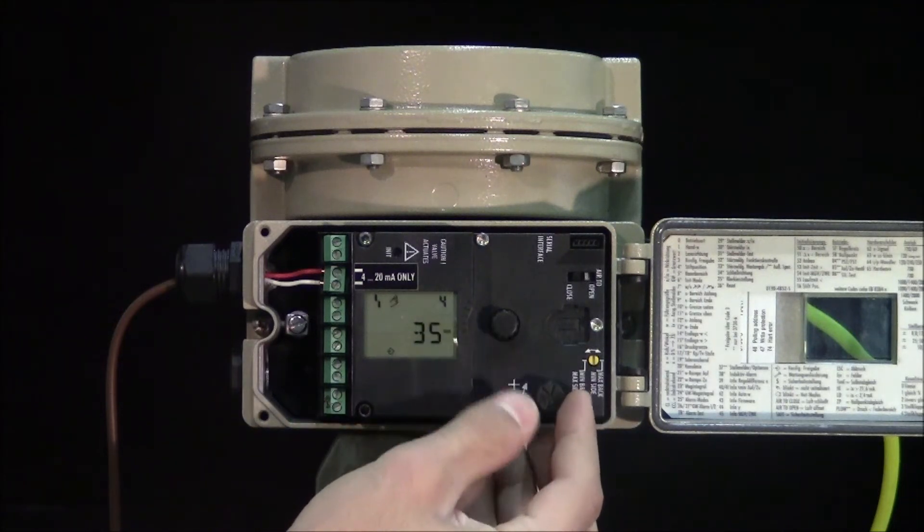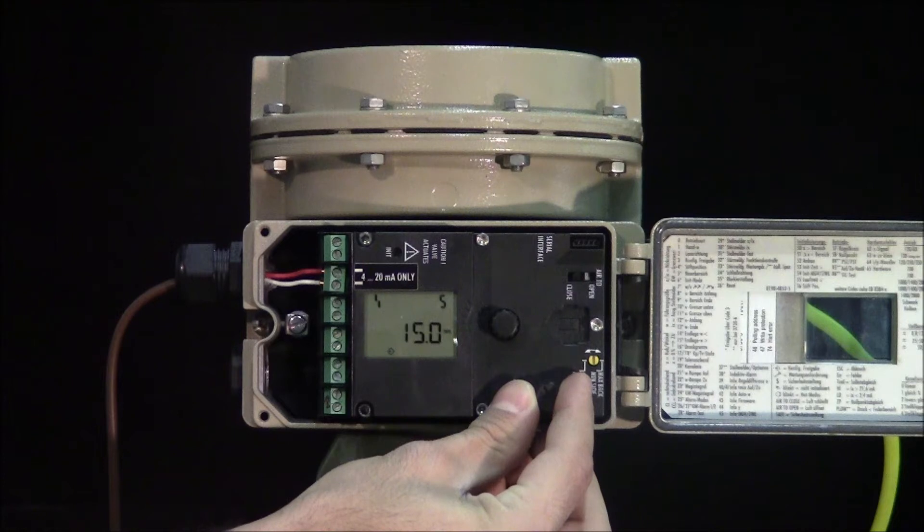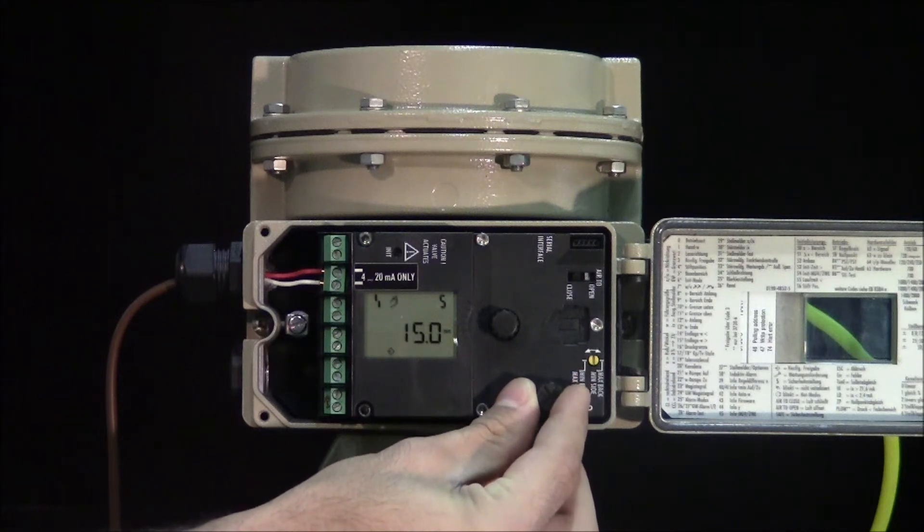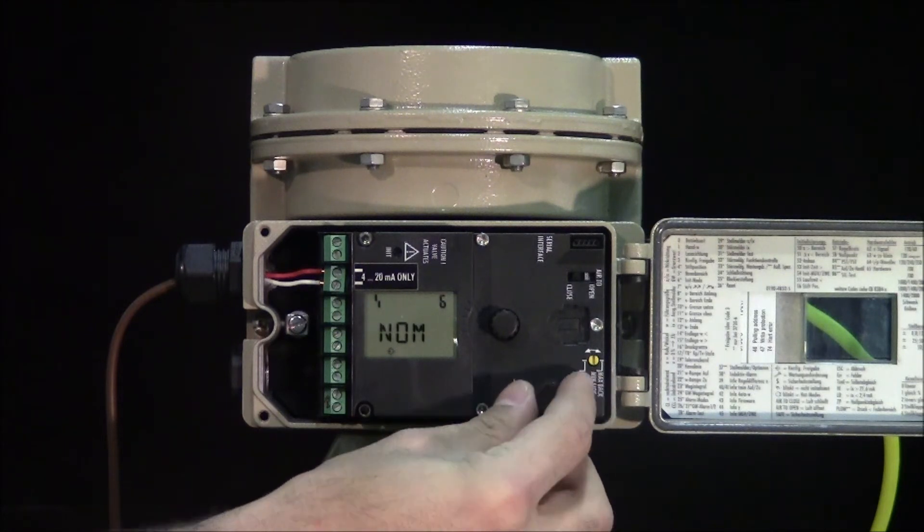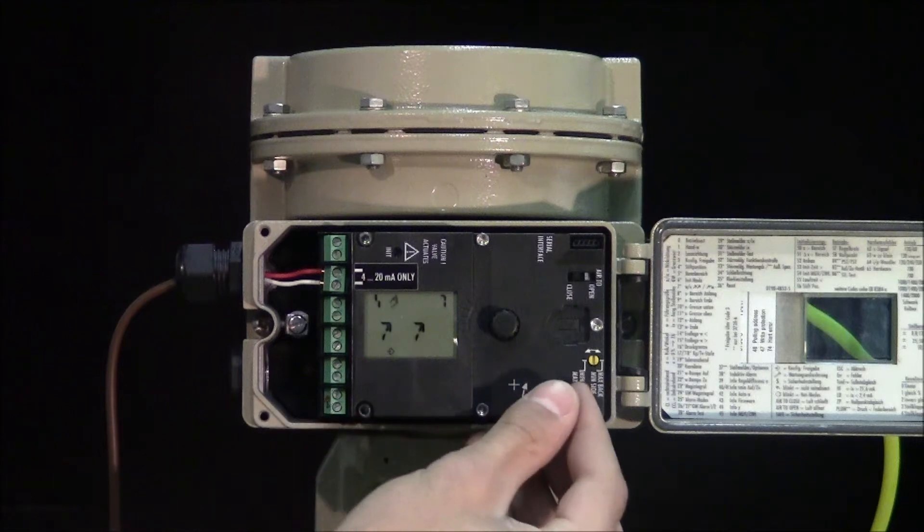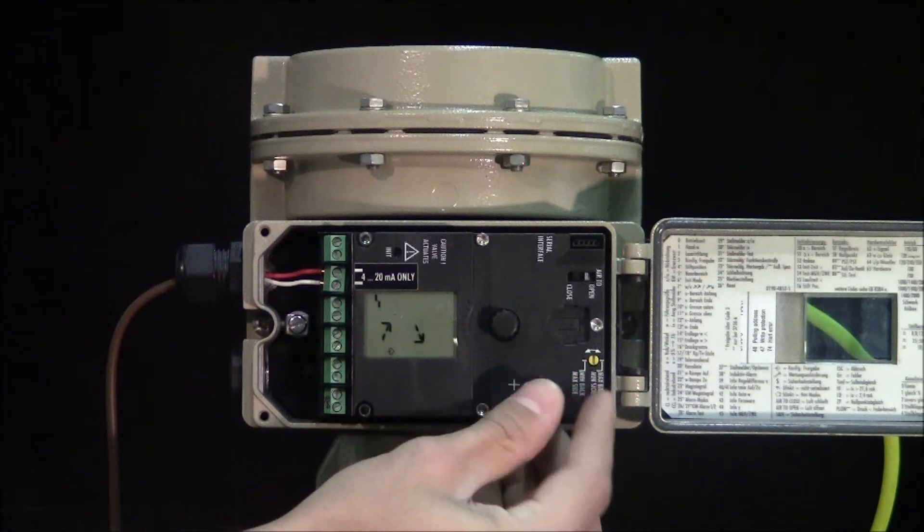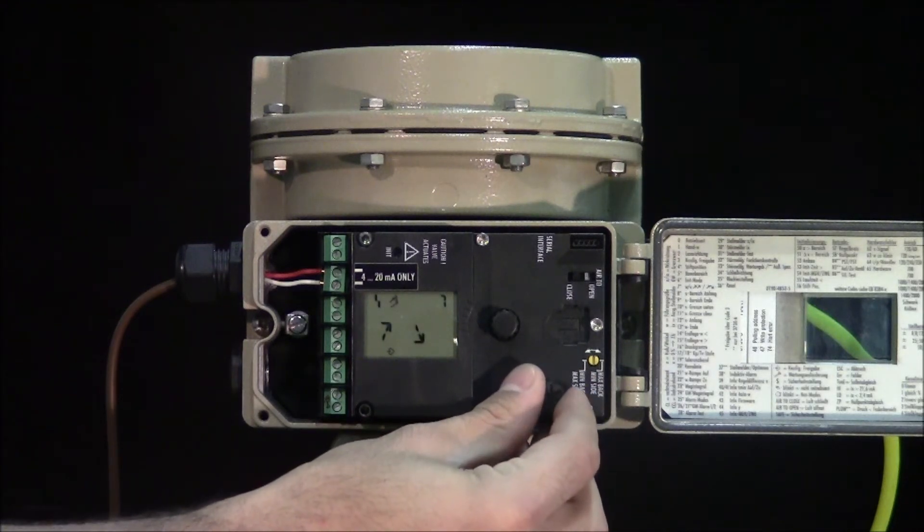Parameter 4 sets our pin position to 35, parameter 5 sets our 15 mm travel, 6 is set to nominal, and 7 changes our operating direction to increasing-decreasing.